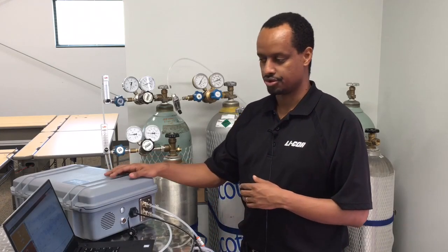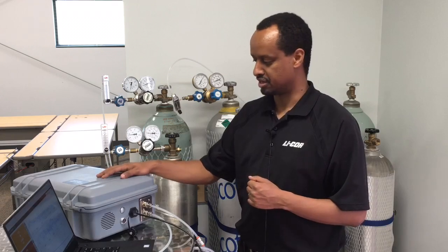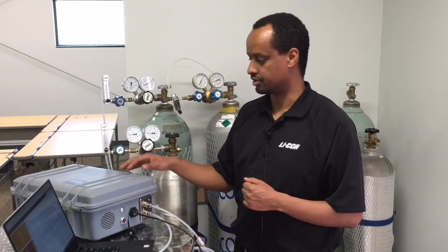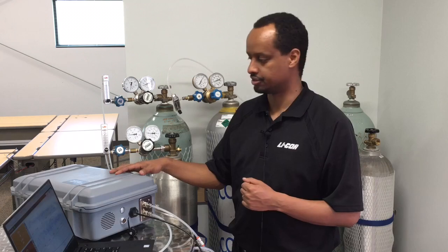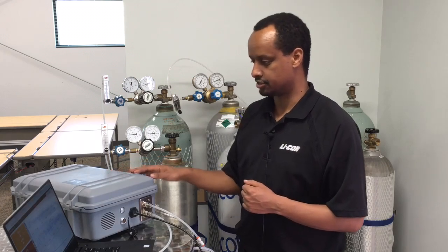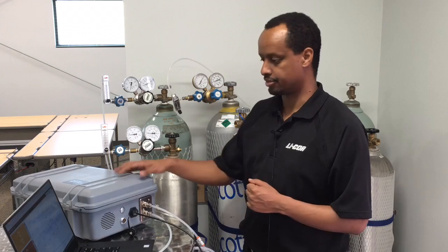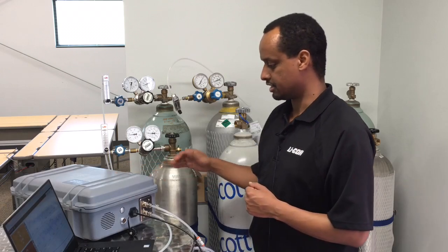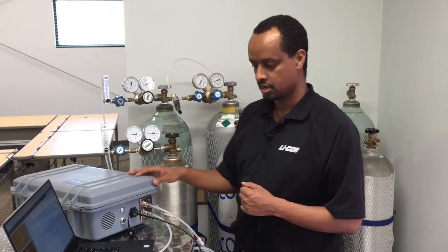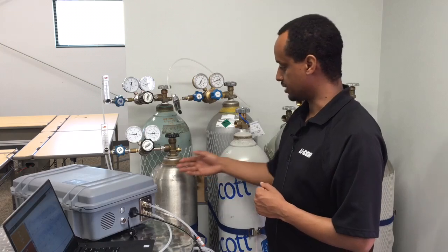Today I want to show you how to do a zero baseline and a span calibration on the LI-7800 series trace gas analyzers. Today we're using the LI-7810, so we'll do a zero calibration, baseline calibration, and a span calibration with methane. We will be using these two tanks.